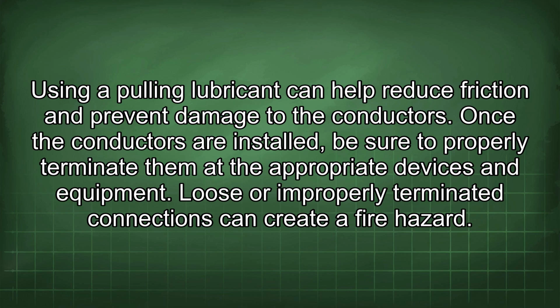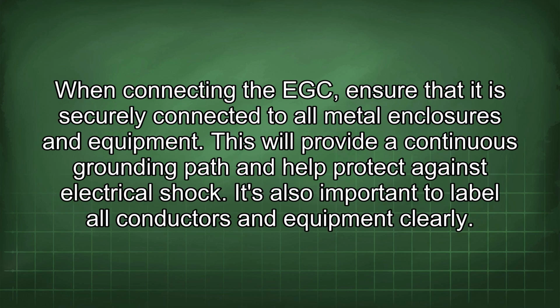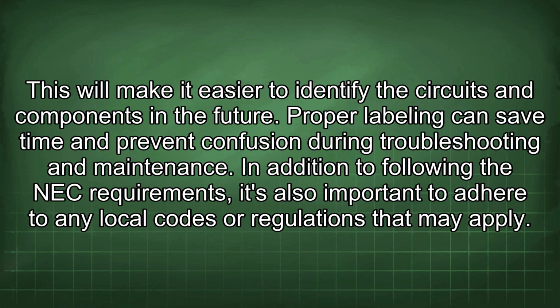Once the conductors are installed, be sure to properly terminate them at the appropriate devices and equipment. Loose or improperly terminated connections can create a fire hazard. When connecting the EGC, ensure that it is securely connected to all metal enclosures and equipment. This will provide a continuous grounding path and help protect against electrical shock. It's also important to label all conductors and equipment clearly. This will make it easier to identify the circuits and components in the future. Proper labeling can save time and prevent confusion during troubleshooting and maintenance.